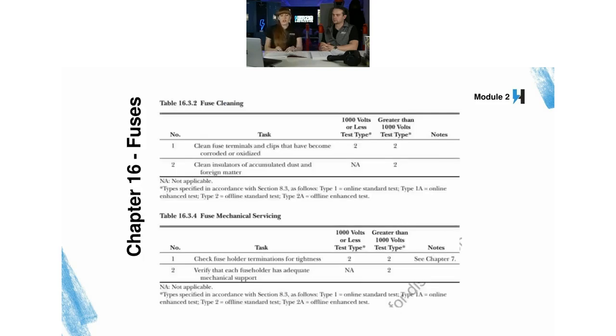So then the next one is fuse cleaning. Clean the fuse terminals and clips if they've become corroded or oxidized. And the second one only is applicable for greater than 1,000 volts. Also to note, the testing categories as well. You've got test category 1 or test category 2. On the screen here, you have clean fuse terminals for 1,000 volts or less. You have a test category of 2, which means you shall clean these fuse terminals while the equipment is de-energized only. Yep. Obviously, you don't want to be cleaning fuse terminals when there's energized conductors.